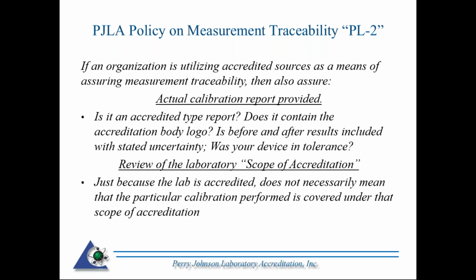So if you're an organization and you go to an accredited source, there are a couple other things you may want to consider. Just because the organization is accredited, you want to make sure that you are getting the accredited type report. In other words, I know some calibration labs have different levels of reporting.